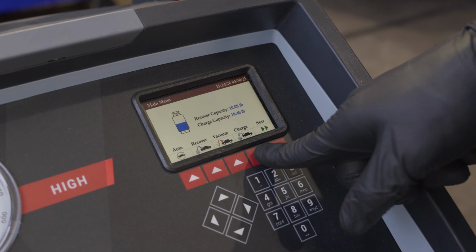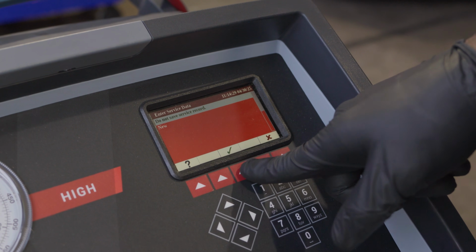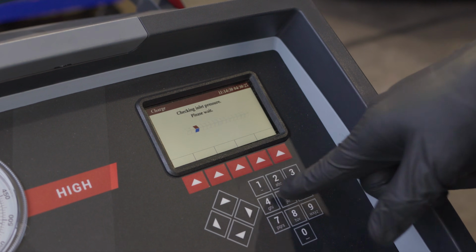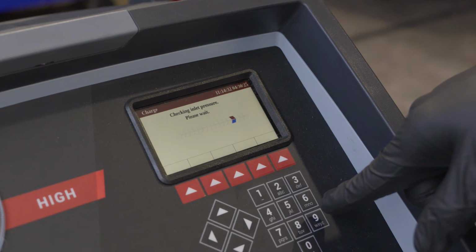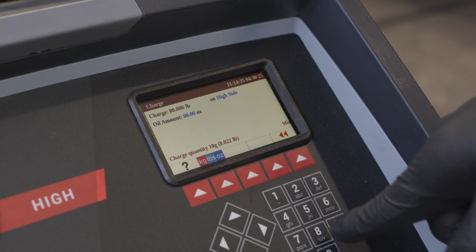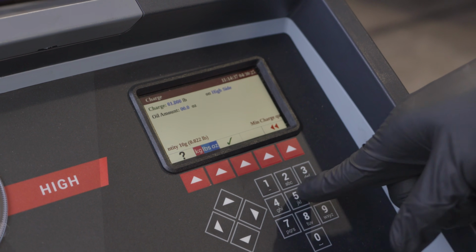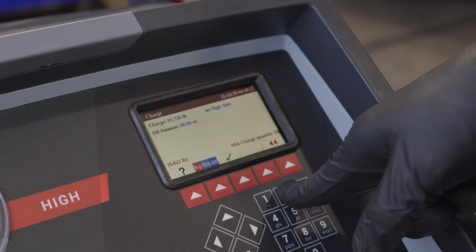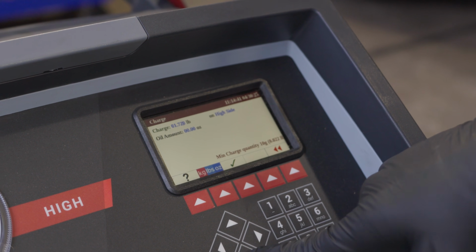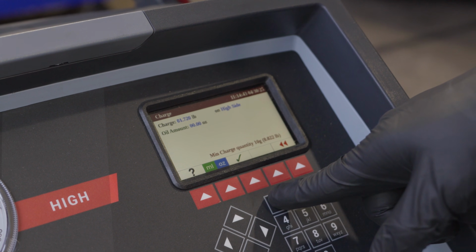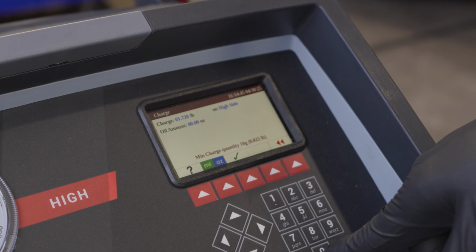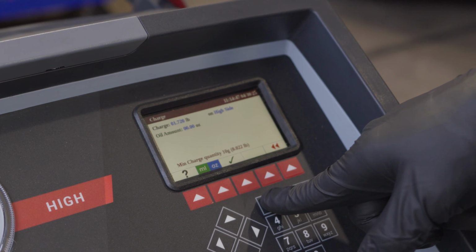We're going to put 1.72 pounds in the system, that's the spec. So, 0.172 pound. And when I charge the system, I always like to put 1 ounce of refrigerant oil in the system.